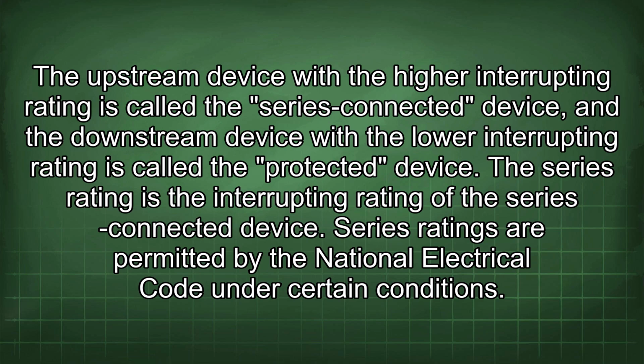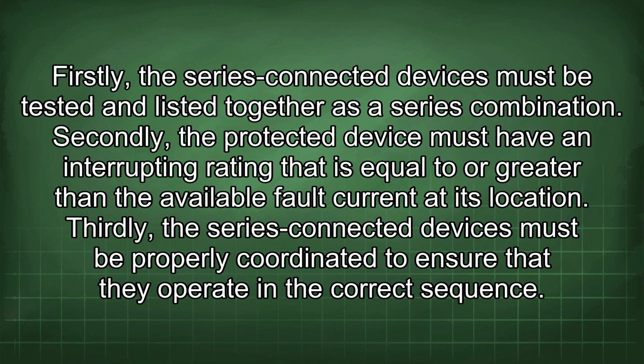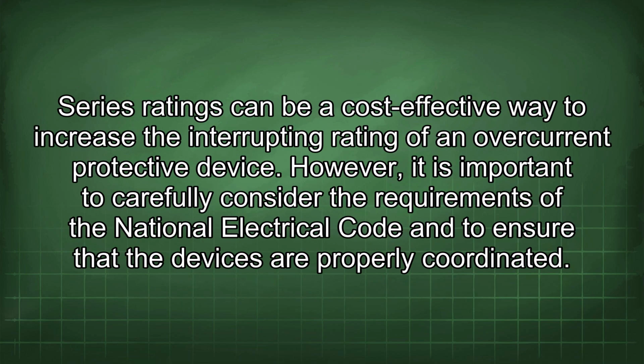Series ratings are permitted by the National Electrical Code under certain conditions. Firstly, the series connected devices must be tested and listed together as a series combination. Secondly, the protected device must have an interrupting rating that is equal to or greater than the available fault current at its location. Thirdly, the series connected devices must be properly coordinated to ensure that they operate in the correct sequence. Series ratings can be a cost-effective way to increase the interrupting rating of an overcurrent protective device. However, it is important to carefully consider the requirements of the National Electrical Code and to ensure that the devices are properly coordinated.